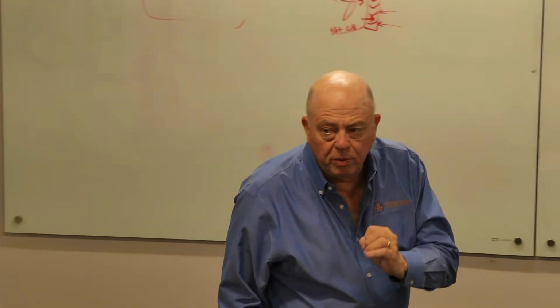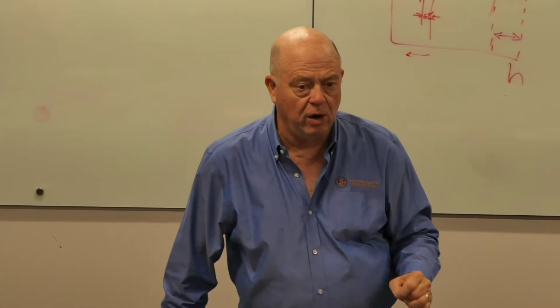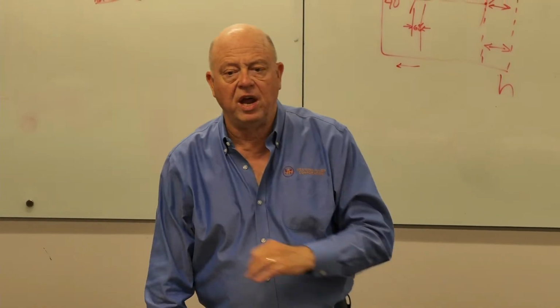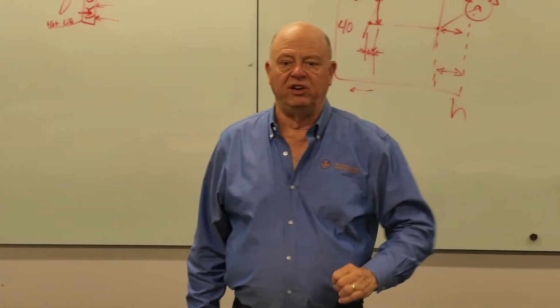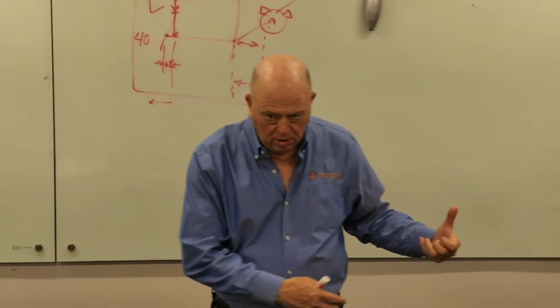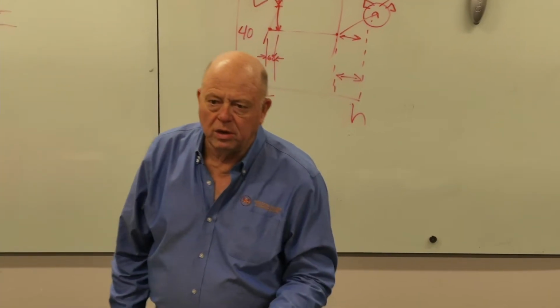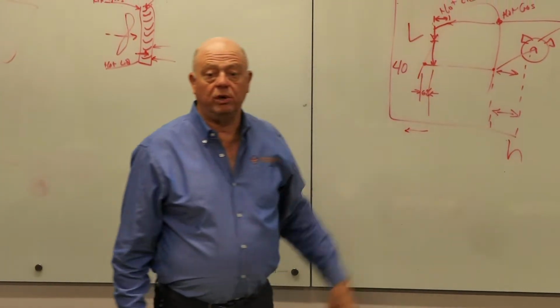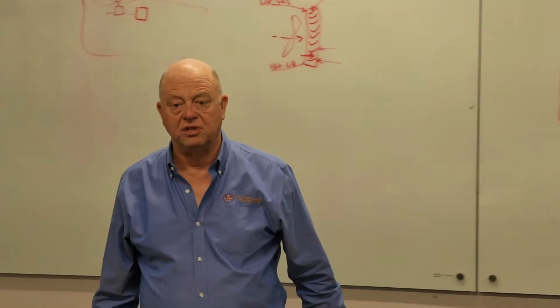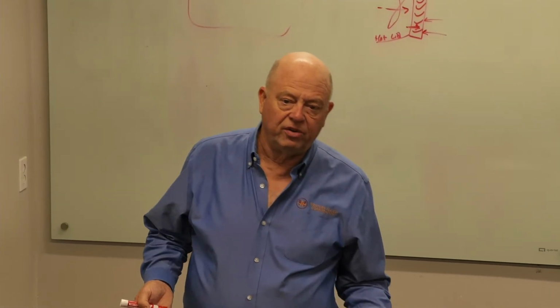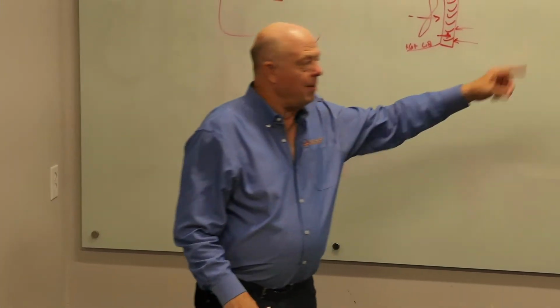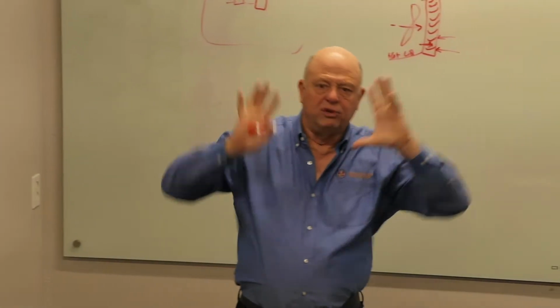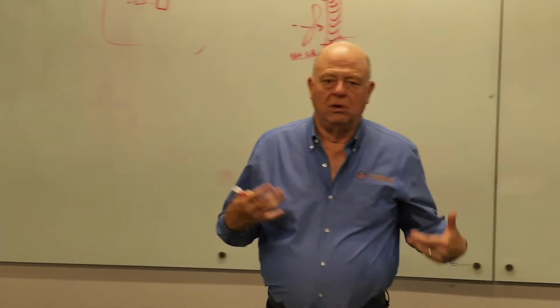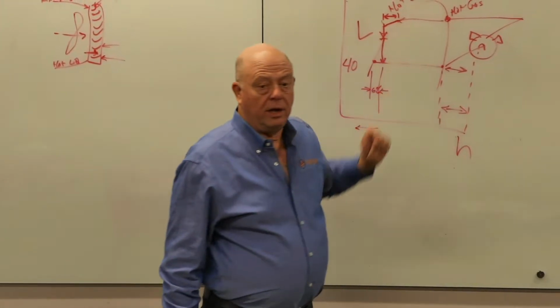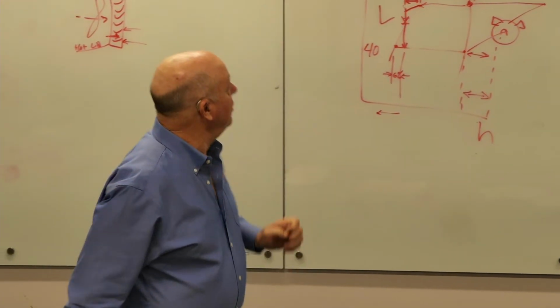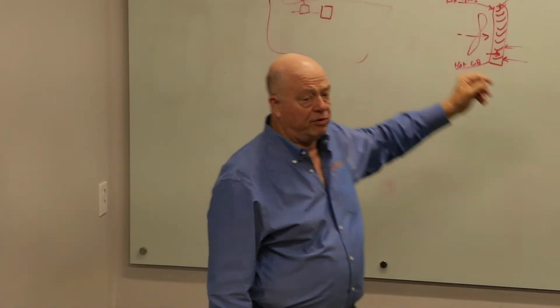The reason the pressure would be the preferred way is it doesn't get faked out. Temperature gets faked out by wind chill. Temperature gets faked out by fog rolling in. Pressure does not get faked out. But a pressure transducer is $300 and a temperature sensor is less than 10. So what do you think the manufacturers want to use? They probably throw in a couple of them and average them, but they're still a lot cheaper than using a pressure sensor. So that's the whole speech on head pressure control.